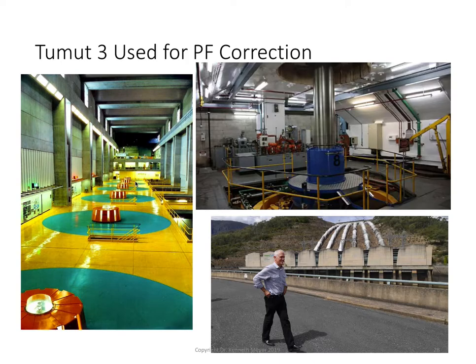And because they can be pumps, it means that we can actually spin them round, not actually make them do any pumping, but if we overexcite their magnetic fields, we can cause the power factor to lead or lag because they're synchronous machines. And if I can create a lagging power factor or a leading power factor, in this case in particular we want a leading power factor, then that can be added into the New South Wales grid and do power factor and voltage correction using what's called a synchronous condenser or a synchronous capacitor.